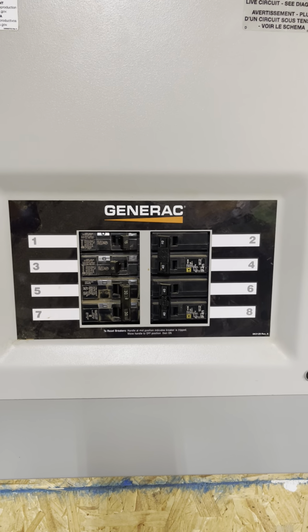And it is fed from 3 XP 6000s. All 3 of those come into a combiner breaker box, which has an individual breaker for the inverters coming back to that load panel. And then I encased all of my wiring in wire trough to make it easy to run stuff back and forth.